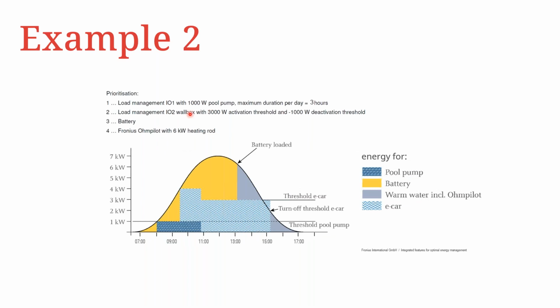We have priority number 1, which is the digital I/O, so we have a pool pump that is running for 3 hours per day. We have another load that is controlled by digital I/O2, which is an EV charger. This has an activation threshold of 3,000 watts, and we are switching it off when we are consuming about 1,000 watts from the grid. And then we still have the battery and the Ohmpilot with a 6 kilowatt heating element. We can see here that the pool pump starts operation just around 8 a.m.